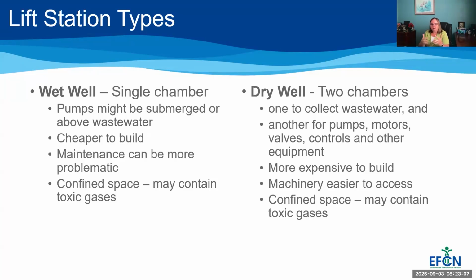So there are some advantages and disadvantages to both. Oftentimes cost is the reason that you're more familiar with wet well lift stations, because they are less expensive to build. However, maintenance can be more problematic. You guys can't see the pumps when they're underwater in your lift station. The wastewater entering our lift stations isn't very clear, isn't quite see-through.